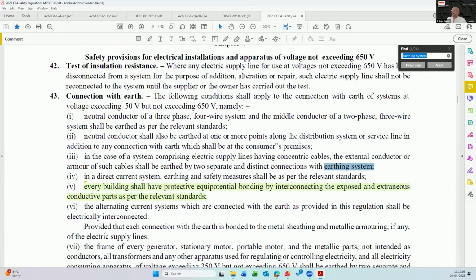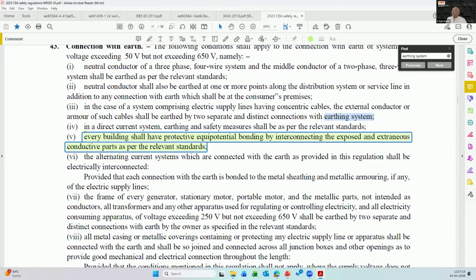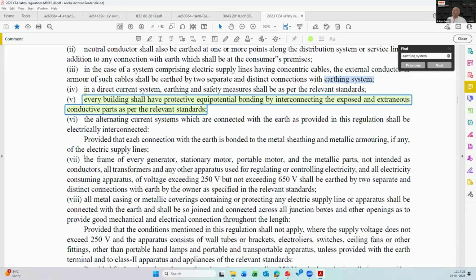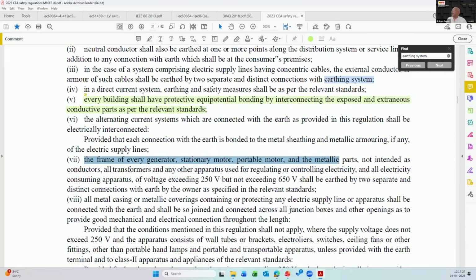So now again regulation 43. Here every building shall have protective equipotential bonding by interconnecting the exposed and extraneous conductive parts. Alternating systems which are connected with earth as provided in the regulation shall be electrically interconnected. For example, the frame of every generator, stationary motor, portable motor, and the metallic parts not intended as conductor, all transformers and other apparatus used for regulating or controlling electricity, and all electricity consuming apparatus for voltage exceeding 250 volt but not exceeding 650 volt shall be earthed by two separate and distinct connections with earth. Please note, not earth electrode. The definition of earth and the definition of earthing system are different.